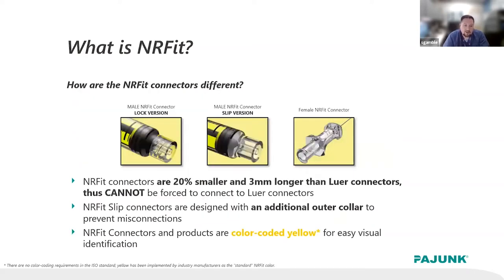So what is NRFit? Well, NRFit are connectors that are actually 20% smaller and 3 millimeters longer than a standard Luer-Lock. Therefore, it is 100% impossible to connect the inappropriate syringe to the inappropriate hub. And so this prevents, as it sounds, the inability to accidentally connect IV tubing, for example, to a neuroaxial connector if the two are not compatible. There is also a yellow color coding system associated with NRFit, so it provides for easy recognition by staff, especially on the fly, or with busy schedules, and this bright yellow coloration helps prevent misidentification of medications or syringes that would otherwise be connected to the wrong system.